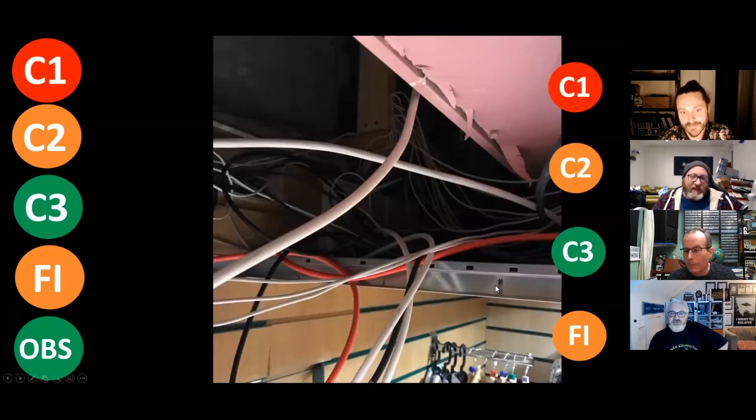Holy mother of... I see this too many times. Yes. Right, so obviously, we've got multiple issues here, haven't we? We've got LV cables mixed with the fire alarm cables. We've got no clipping. And how many times do you look up above the ceiling and it looks like this? That's a retail shop, isn't it? It's a suit shop. That's just awful. And you're right. I've been in local suit shops where I live, and the electrics there are dire, and nothing's compliant. Everything's lassoed across ceilings.